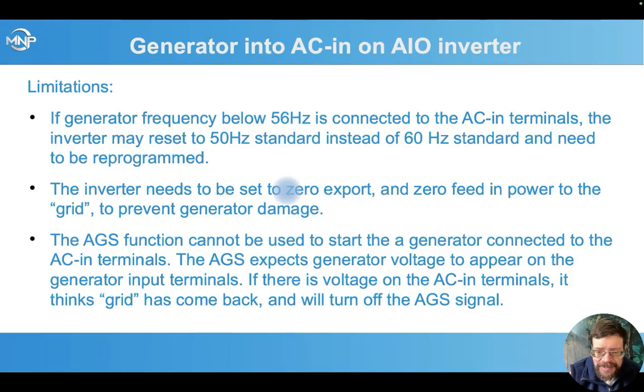And that's because the AGS, when it tries to start a generator, expects that generator voltage to show up on the input terminals. If there's voltage on the AC in terminals, it says, oh, the grid came back, I don't need to run the generator, and it turns off the signal, and then your generator will stop. So it just gets all confused. We are working on some newer firmware where you can select the AGS function to work with either of the inputs. So coming soon, that will be changed. But for now, the AGS function only works on a generator connected to the generator terminals.